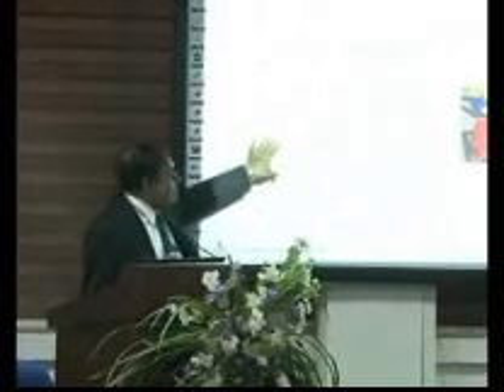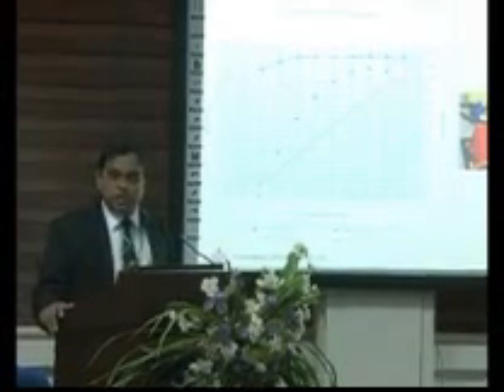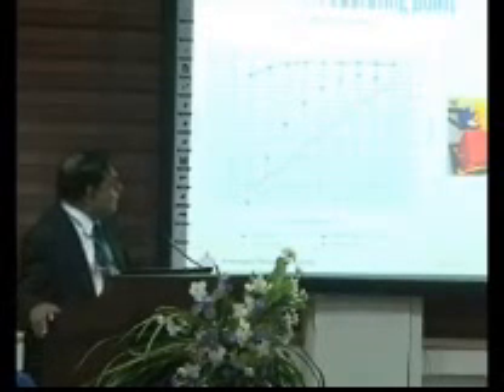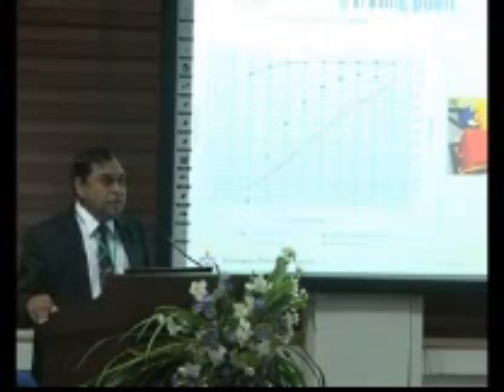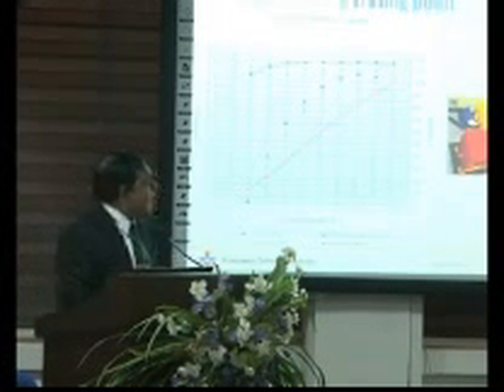But if the discharge reduces to 30%, the efficiency drops to 65%. So you need more water to get a kilowatt hour if you are operating there. Mini hydro plants don't have the option to avoid this, because they don't have a reservoir, so they depend on the amount of water available at the time, and the operating point is decided by that. But in plants where we have reservoirs, we have flexibility to operate at better points and get more energy from the same water.